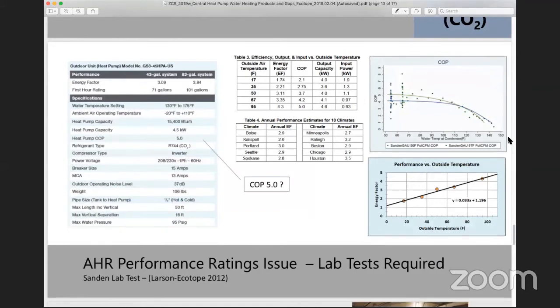You know how these single pass CO2 devices work. They're gas coolers, but they're really efficient at really cold entering water, and that's why you want to set up these single pass devices - as you can see on the COP chart, they start out at 5 and race down to 1. So when you get to temperature, you're at COP1, and when you're just starting out, you're at 5. Setting these up with the coldest possible water entering is really the game on efficiency.